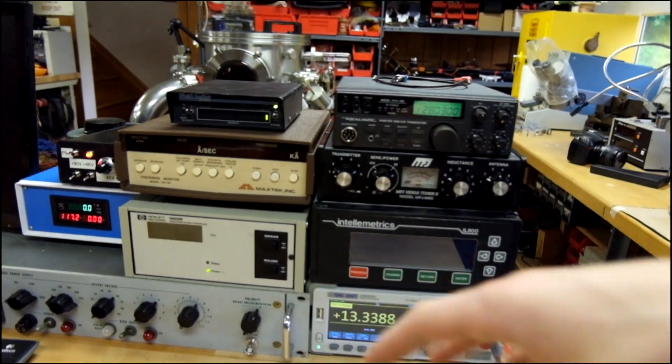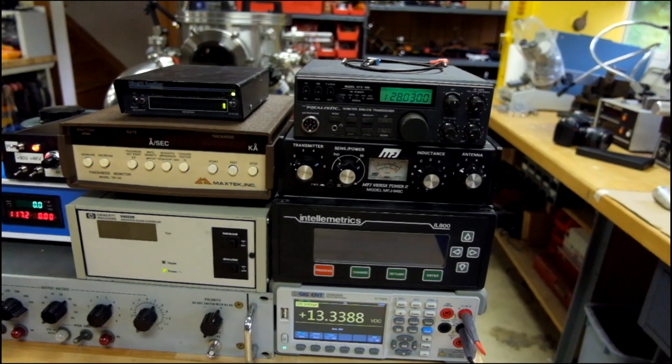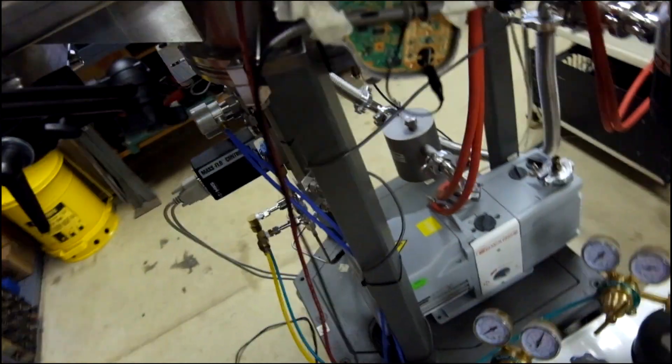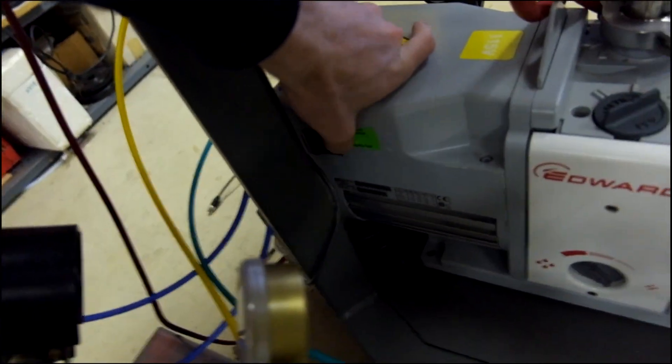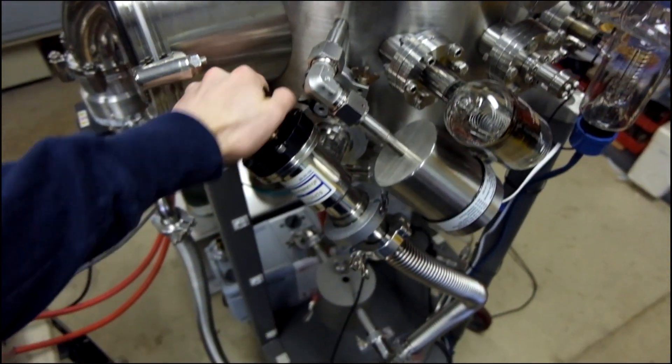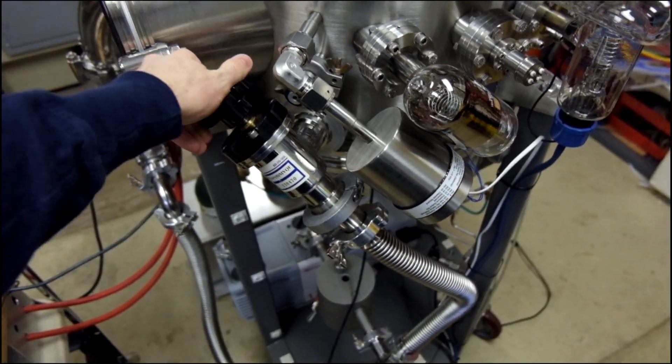So now I have all the gauges on and I'm going to go ahead and turn the mechanical pump on and that's going to start the pump down. That's going to take about 10 minutes and it'll pump down to about 50 millitorr. Then I'll pump down a little bit more and we'll start the turbo. So hit that guy and then I'm going to open up the isolation valve so it can actually start pumping from the chamber.